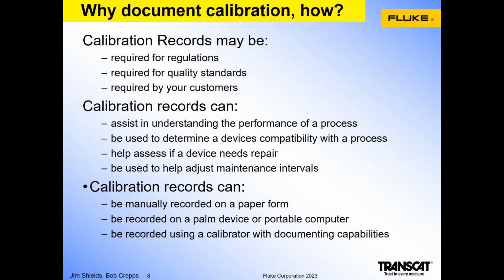So why document and how? Calibrations may be required for regulations, required for quality standards, or required by your customers. They can assist in understanding the performance of a process over time, and can be used to determine if a device is compatible with a particular process. If it's consistently out of tolerance, it may need to be replaced with an appropriate device. It also helps assess if a device needs repair or replacement.